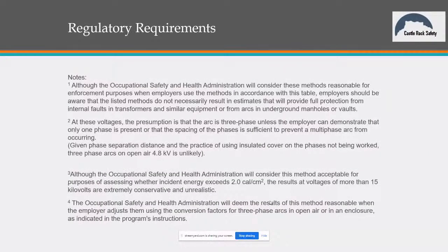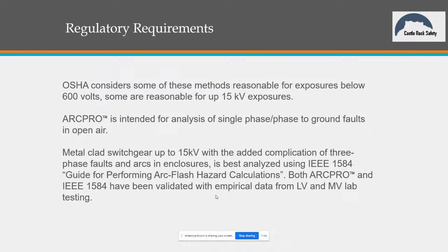Anyway, these are some notes to the table about how, given phase separation, 3-phase arcs in open air are very unlikely to happen. It seems like that's the concept behind what we run out in the plant. It's called an NGR, neutral ground resistor, and that's basically set up only for a single phase event, like an energized conductor to ground versus energized conductor line to line. Right. Now you may get an arc or a fault across 2 phases, but that's still considered single phase. It's really not likely to ever have a 3-phase event in open air on a line or a bus. They even say a line to line is pretty rare. It is, but it's certainly more likely than a 3-phase.